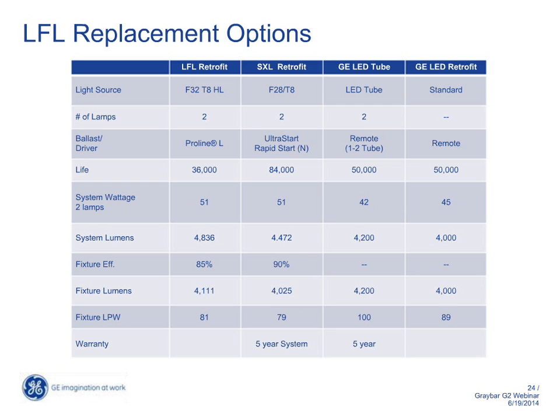So efficiencies are there with LED tubes. You can get long life also with fluorescent. 84,000 hours on fluorescent, though, means that there is a mortality curve. Not every single lamp makes 84,000 hours. It typically means half the lamps have failed by 84,000 hours. So something to keep in mind. We really don't expect LEDs to fail within that 50,000 hours life that's frequently claimed.